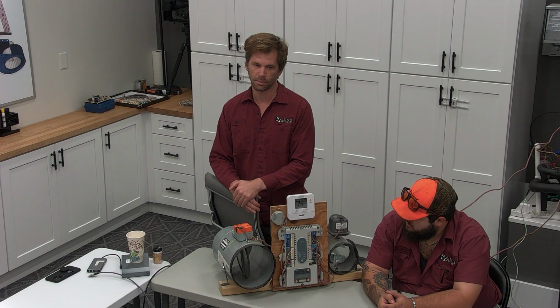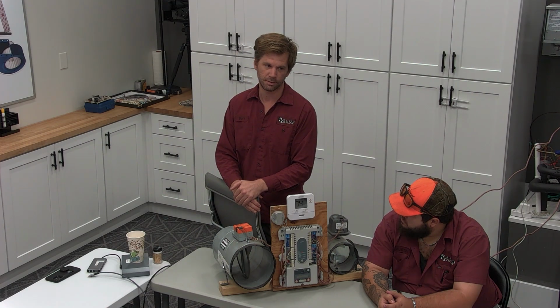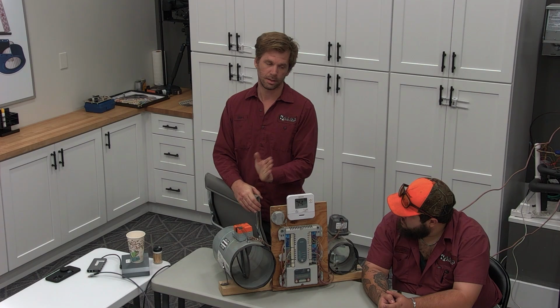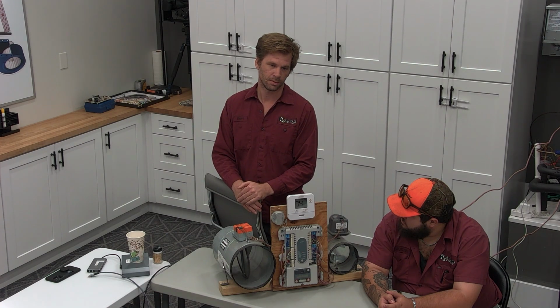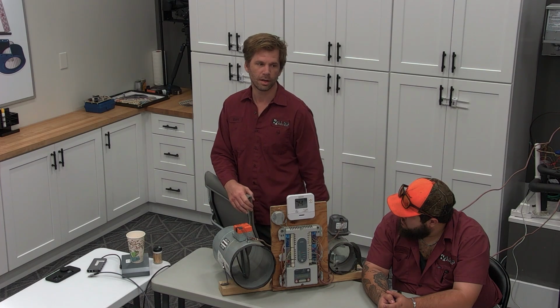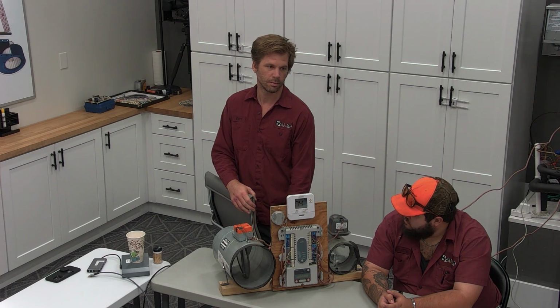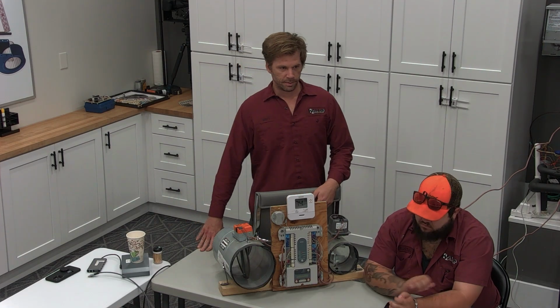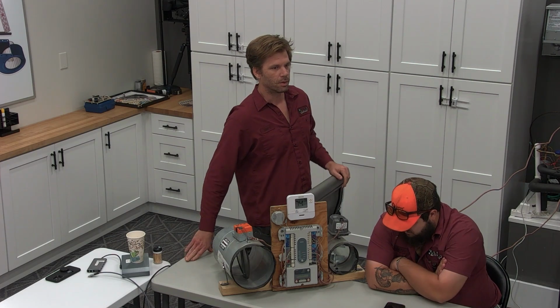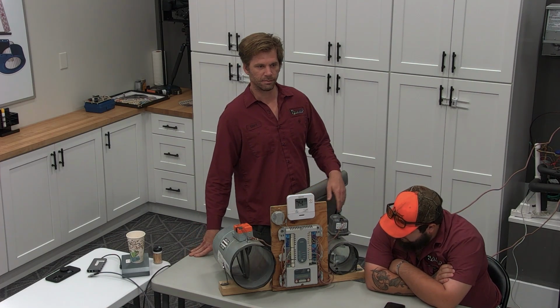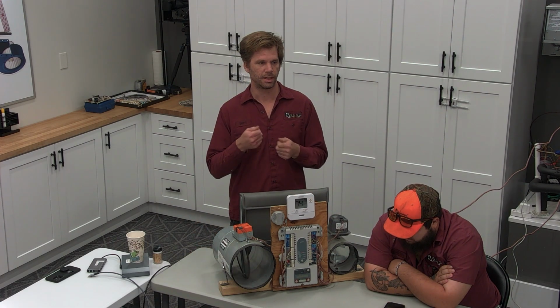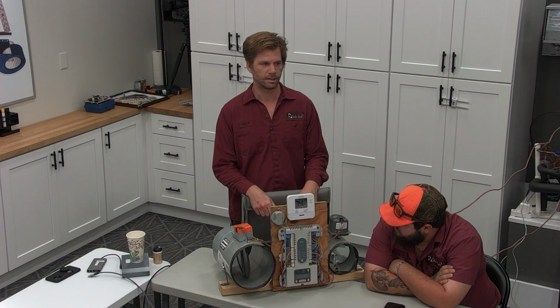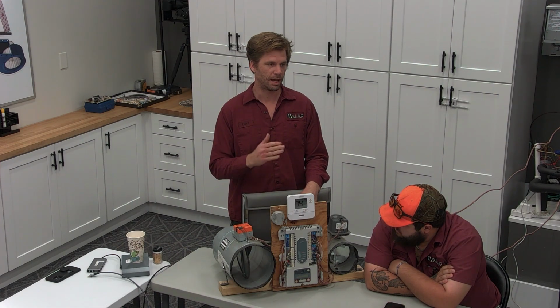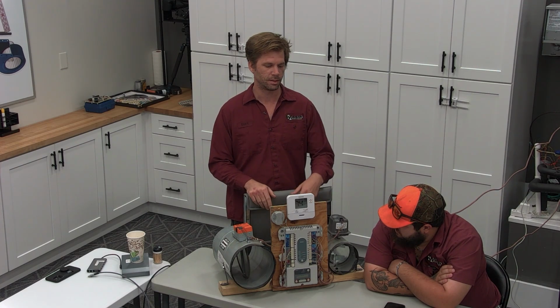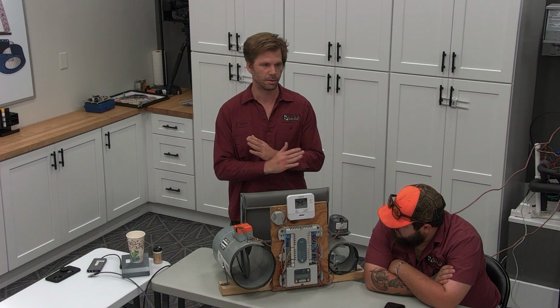The only difference, which is a little bit tricky, and I failed a board that wasn't failed for this, is that when it's done turning, it stops sending the signals. So the board will only send the 24 volt signal long enough that it thinks the damper gets open and closed. And you can confirm all that through the airflow verification test. Yep, and exactly, they will confirm themselves based on static, whether it's opening and closing. But if you're there trying to figure out, is my damper board failed, what's going on here, it's not sending the signal to open, or it's not sending the signal to close. It's only after that initial command change, long enough for the motor to turn, and then it shuts off, stops sending the signal. Whereas this, and pretty much every other board, constantly energizes open or close.